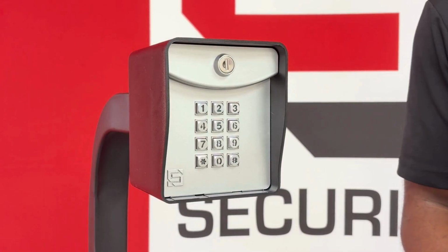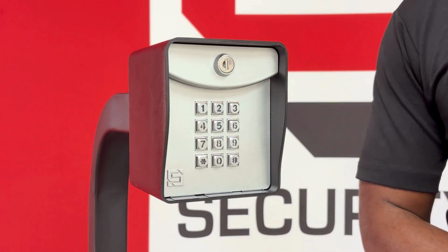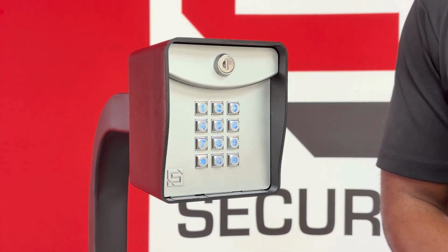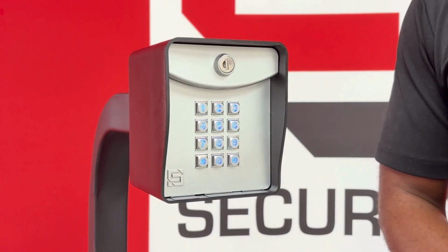Next, we're going to be showing you how to delete an access code from your Ridge keypad. Again, for this example, we'll be using the default master code, which is 1251. Then we're going to enter submode 2, which is for deleting a code. And we'll delete the code 1414.